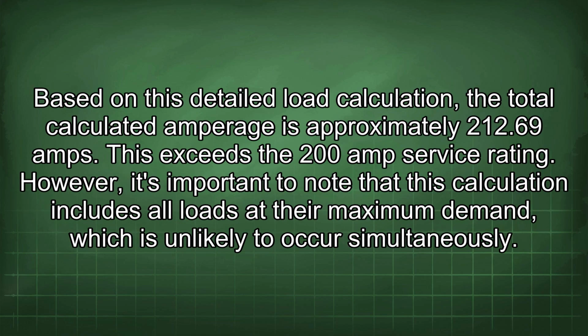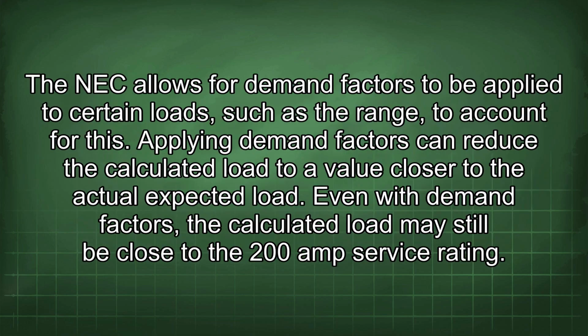Based on this detailed load calculation, the total calculated amperage is approximately 212.69 amps. This exceeds the 200 amp service rating. However, it's important to note that this calculation includes all loads at their maximum demand, which is unlikely to occur simultaneously. The NEC allows for demand factors to be applied to certain loads, such as the range, to account for this. Applying demand factors can reduce the calculated load to a value closer to the actual expected load. Even with demand factors, the calculated load may still be close to the 200 amp service rating.